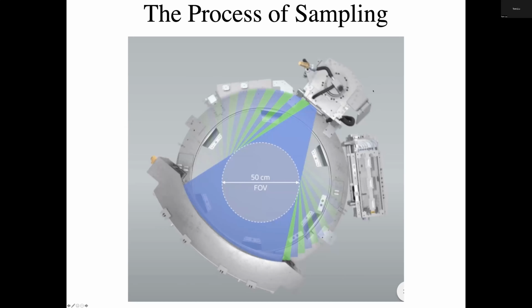The geometry of this detector and how it's set up in a scanner in which the source rotates around the patient looks like this. You have an X-ray source. It pushes out this fan beam, okay, of X-rays. Normally, it doesn't flash the X-rays. Normally, it just keeps them on constantly.